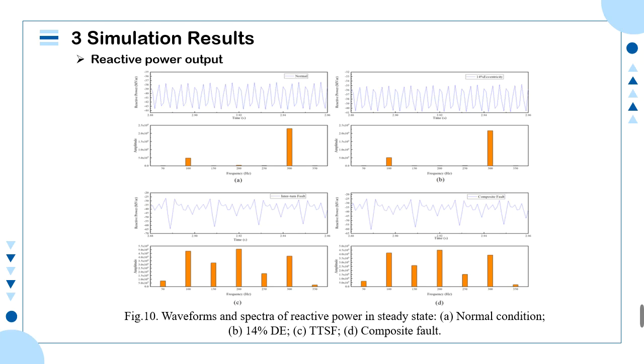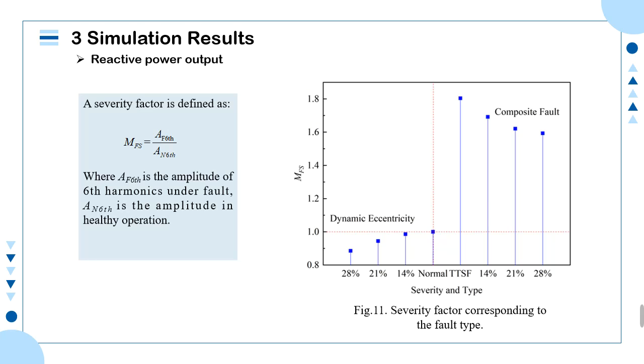The waveforms and component spectra for reactive power output are displayed in Figure 10. It infers that once TTSF happens, the odd-order component will emerge in the capacitive reactive power outputs. Because there are apparent 6th harmonics in every case, the following index is defined to indicate the severity of the faults. The tendency of this index is shown in Figure 11.